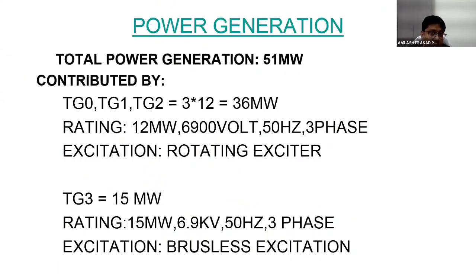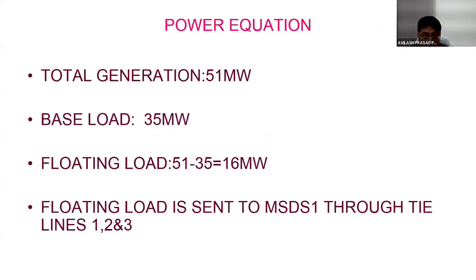Further, coming to details about this captive power plant, the total power generation through this captive power plant is 51 megawatt. As said earlier, it is contributed by TG0, 1, 2, 12 megawatt each, that is 36 megawatt. The rating is 12 megawatt, 6900 volt, 50 hertz, 3 phase. Excitation is a rotating exciter. TG3 is rated 15 megawatt, 6.9 kV, 50 hertz, 3-phase, and excitation is brushless excitation. The total generation is 51 megawatt. Our base load is 35 megawatt, and floating load is 16 megawatt. So floating load is sent to MSDS1 through tie lines 1, 2, and 3, which I have shown earlier.